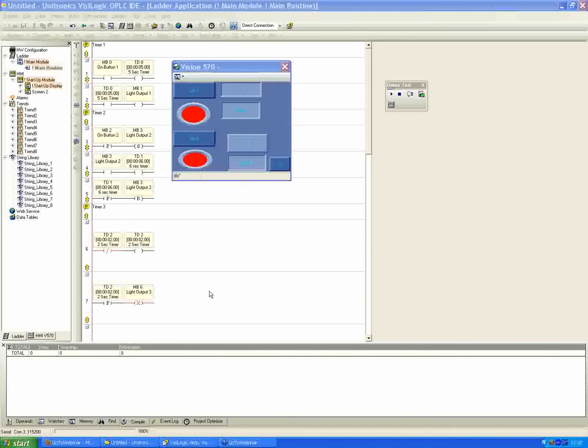The second thing: if you use the memory bit as a link to a push button to perform a jump, it operates as a positive transition. When it performs the jump and goes to another display, the operating system of the controller resets it. That's why, I guess, the push button doesn't work in the ladder — though I cannot see Wendy's ladder to know exactly what she did.